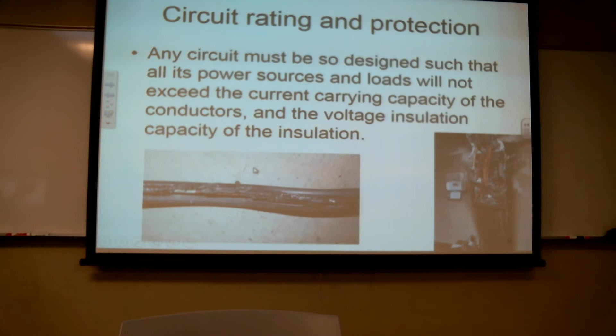Another way of saying this is the circuit protection is designed to protect the circuit, that element or component it serves. Which means if I design the circuit for 50 amps, the circuit breaker needs to blow at something below 50 amps, right?